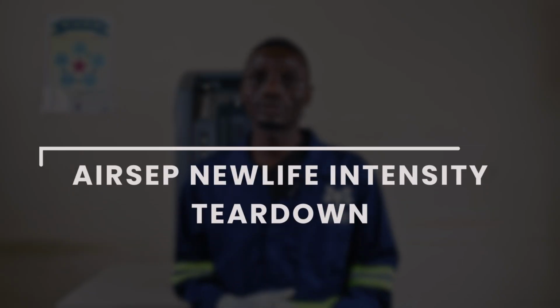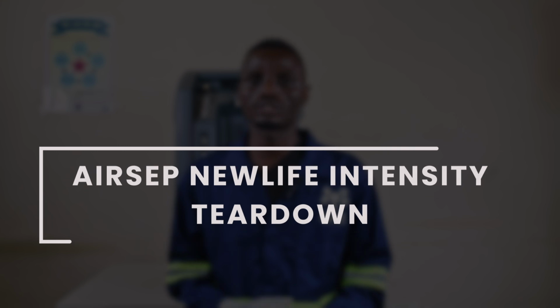Today, we'll tear down an AirSep New Life Intensity Oxygen Concentrator. The AirSep oxygen concentrators normally operate at voltages ranging from 220 to 240 volts AC and at a frequency of 50 Hz. For this oxygen concentrator, it operates on 230 volts AC at a frequency of 50 Hz. It has a capacity of 10 liters per minute and can deliver up to 95.6% oxygen purity at flow rates ranging from 2 to 10 liters per minute.